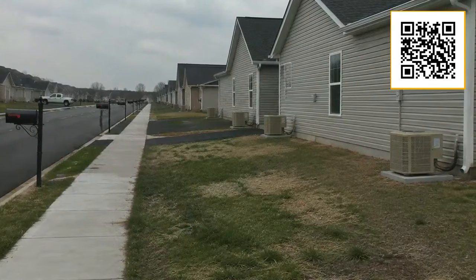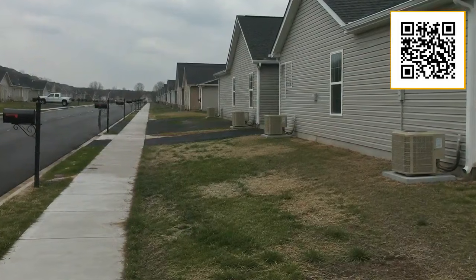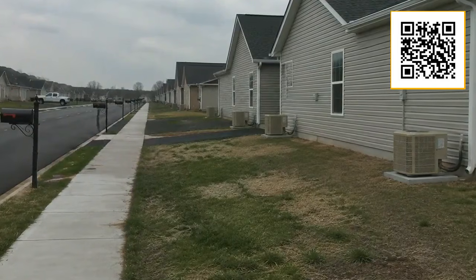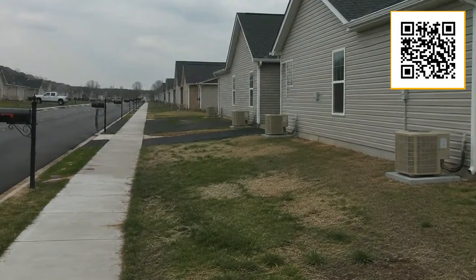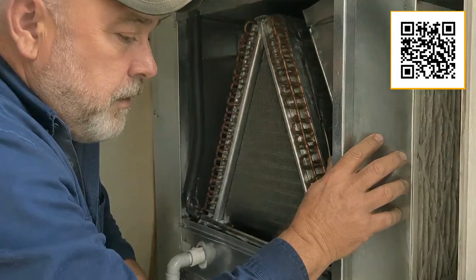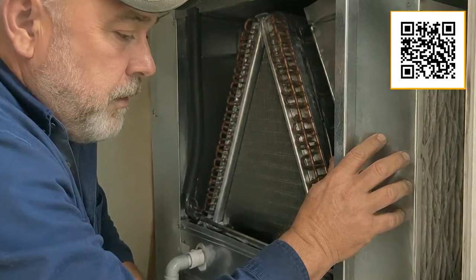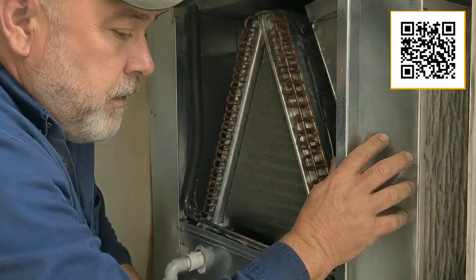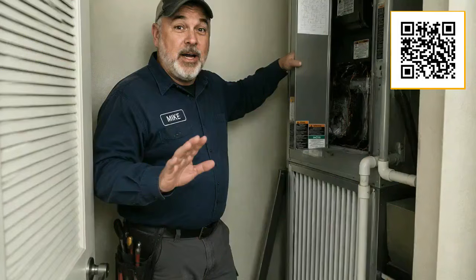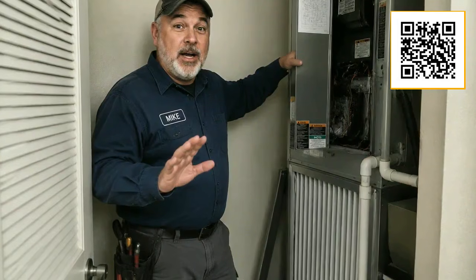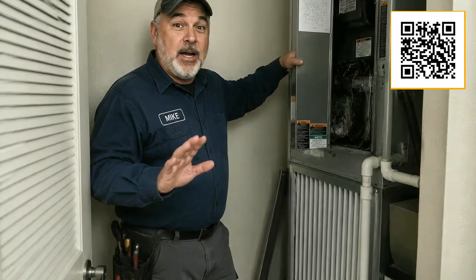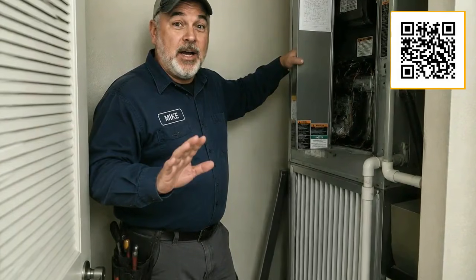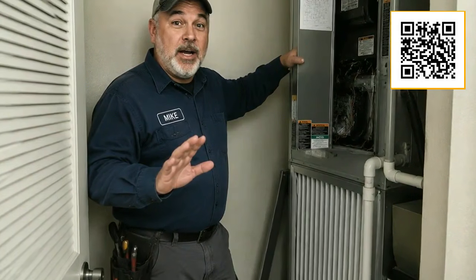The second type I see fail constantly is cheap builder-grade equipment. When a home is built by a developer and the HVAC system is chosen to hit a price point rather than serve the homeowner, you usually end up with entry-level equipment that looks fine on paper but is built to the absolute minimum standard. I am not going to name brands because the specific names change over time and vary by region, but you will recognize the pattern.